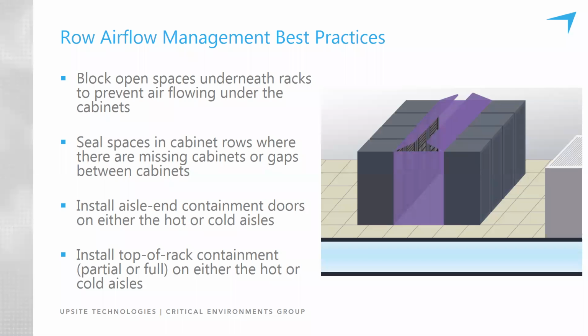And lastly, the top of rack containment. Hot aisle containment typically features an above rack barrier around the perimeter of the hot aisle and typically extends upwards from the racks to the top of the ceiling, or vice versa from the ceiling down to the top of the racks. And cold aisle containment could involve a roof or a capped aisle or even a partially capped aisle that spans across the cold aisle. And again, more to come on both of these as we get into the presentation.